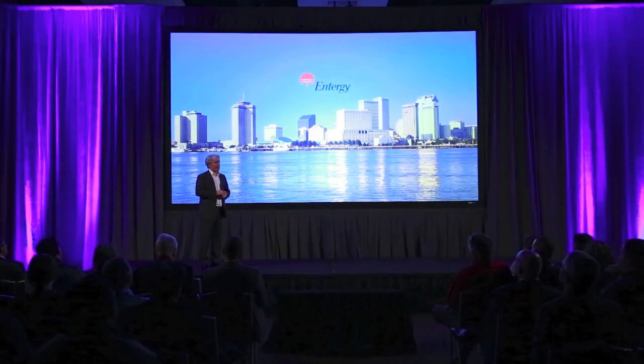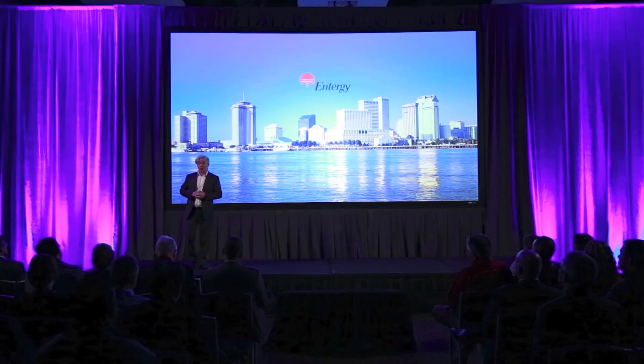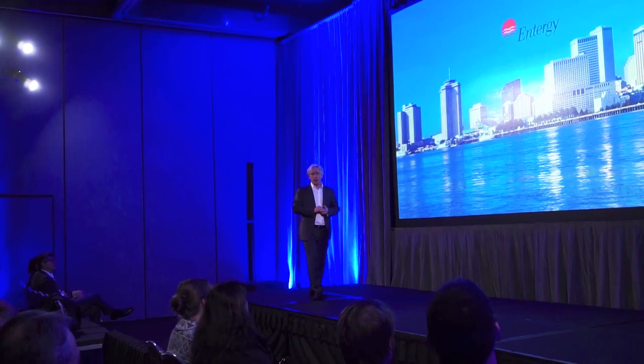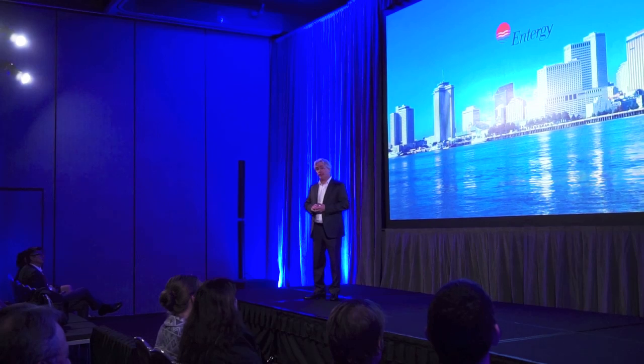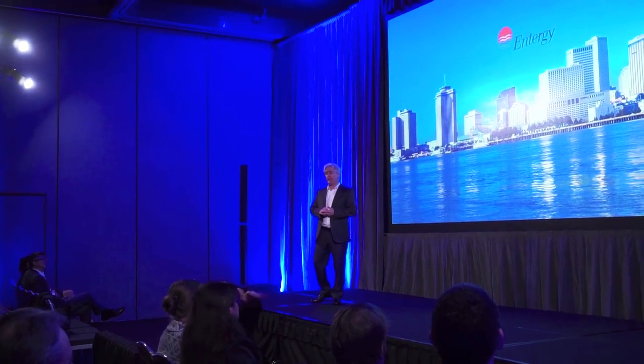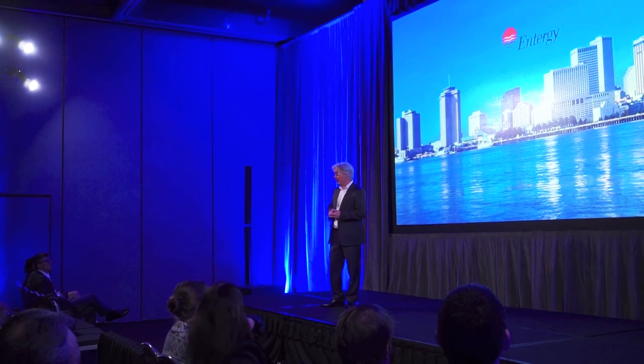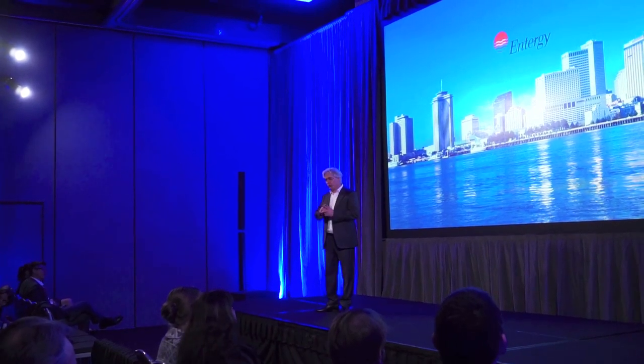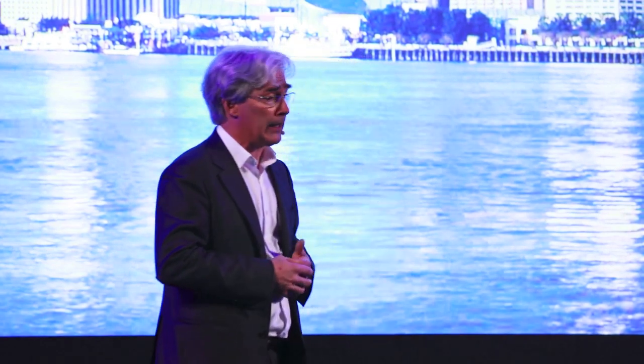A few years ago, Entergy, a southern utility, decided to deploy several Callisto 9 monitors. One of these monitors was installed on a new transformer and detected dangerously high levels of acetylene and methane as soon as the transformer was energized. Entergy confirmed the Callisto reading on-site right away using a portable DGA analyzer. They also sent an oil sample to their lab and to Morgan Schaffer to confirm that the Callisto 9 was measuring accurately. Upon confirmation of the readings, they took the transformer out of service.